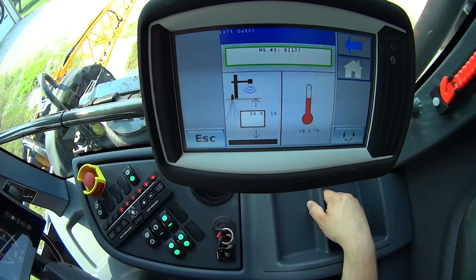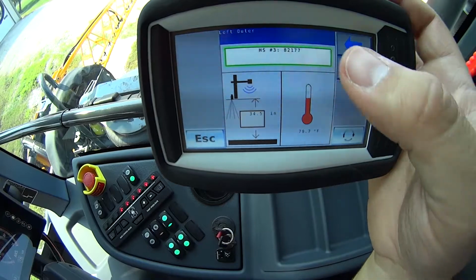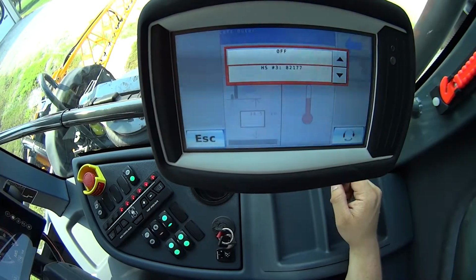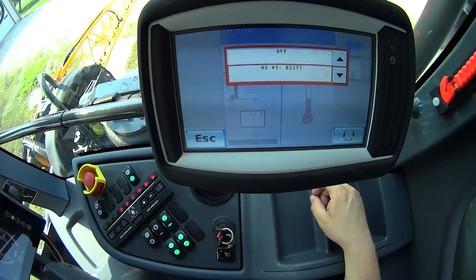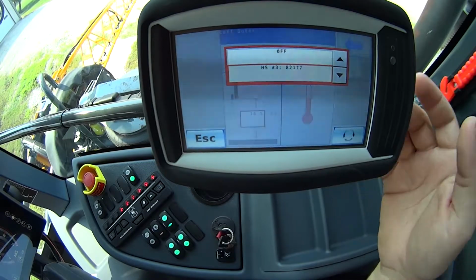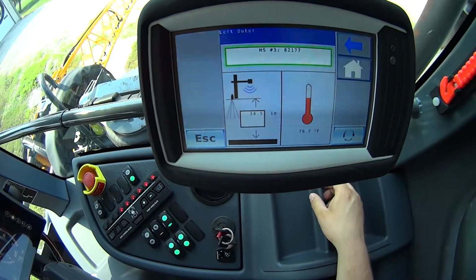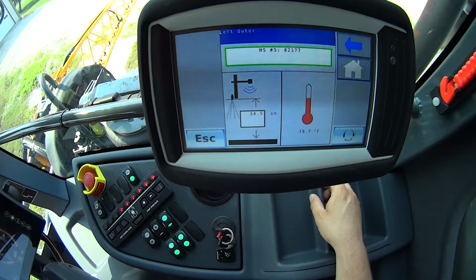This is where I can go and change sensor locations. So if I needed to change around a sensor or replace a sensor, or in a troubleshooting process I've moved a sensor from one location to another, I would use that by tapping this drop-down box. By selecting off, I can go in and select any unassigned sensors. This system, all the sensors are assigned, so I'll just pick the correct one there.